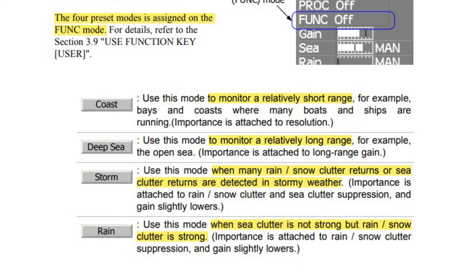Storm — use this mode when many rain/snow clutter returns or sea clutter returns are detected in stormy weather; importance is attached to rain/snow clutter and sea clutter suppression, and gain slightly lowers. Rain — use this mode when sea clutter is not strong but rain/snow clutter is strong; importance is attached to rain/snow clutter suppression.